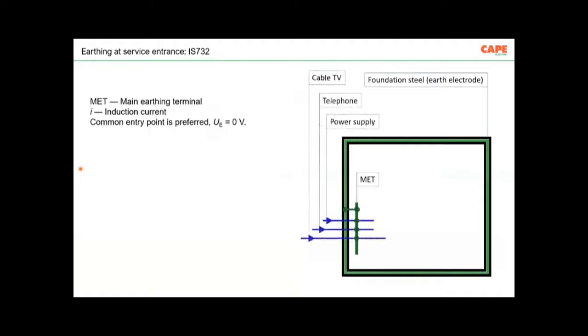Every building at the service entrance, that means at the main switchboard, whatever metallic services are coming from outside, we are supposed to create an equipotential bonding. In the picture, what I am showing is a metal water pipe, gas, sewage pipe, telecommunication, power supply, and so on. This has actually got three purposes.